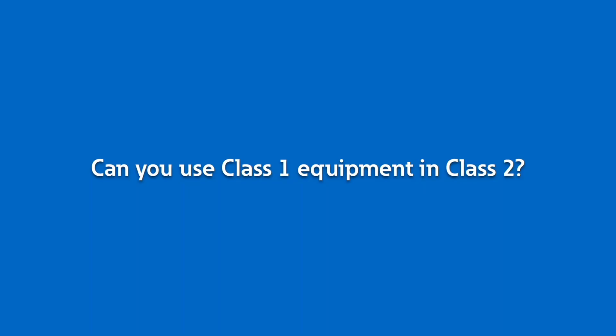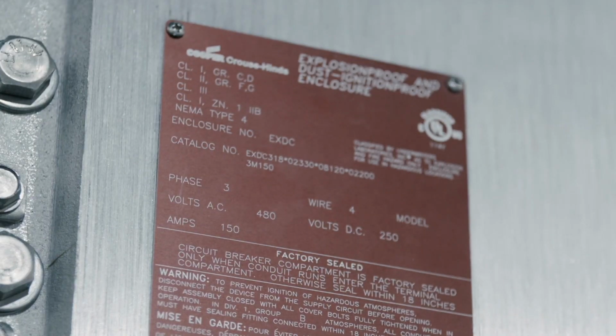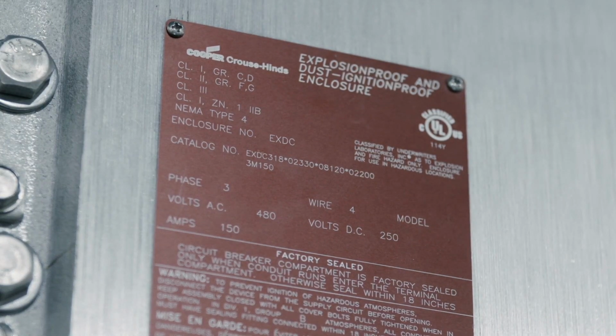You can use Division 1 equipment in a Division 2 location, but the certification testing is more stringent. However, you can't use Div 2 equipment in a Div 1 location. Class 1 is for gas locations and Class 2 is for dust areas. However, some equipment has both Class 1 and Class 2 markings on.